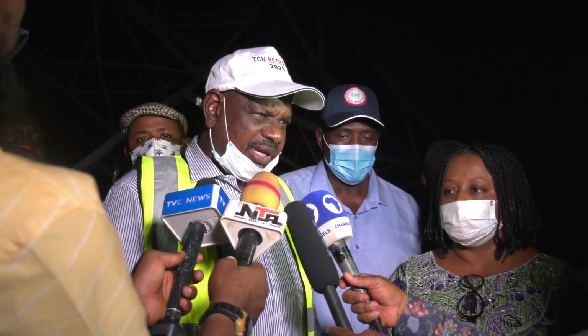So Akangba station, which is fed by this line, also has another source where we can feed it, which is through Ijora. So from that time, we have been supplying the substation through Ijora, and now our engineers were able to restore the second line that tripped, because this line that went down is line 1. Then we have line 2 in case of redundancy. That line, when this incident happened, also tripped. But our people have patrolled the lines, it is now working, and all the load has been transferred to that line. So we don't have any problem. Even as of today, Lagos is getting almost 900 megawatts.